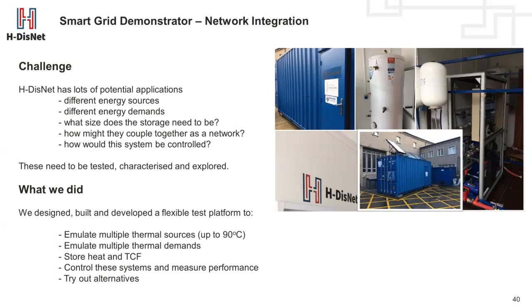Within it, we can test and create the conditions of multiple thermal energy sources from up to 90 degrees C, and we've also gone the other way, down to about 30 degrees at the lowest. Within that system, we can emulate different thermal and air conditioning loads, and we can store the heat as heat, or store it within the thermochemical fluid itself for recovery when we need or want to use it.